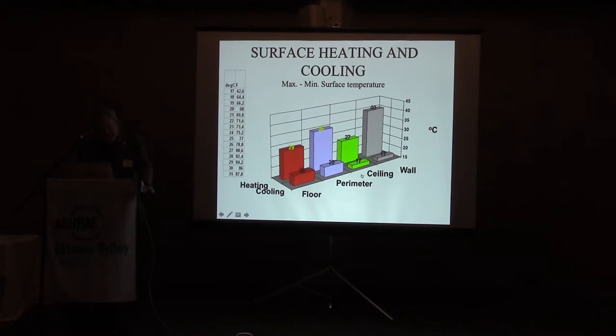Well, the ceiling, we don't have any parts of the body which are in contact with the ceiling. So here, the limitations for the heating part are the rate and the symmetry. People don't like to have a warm head and cold feet. The other way around, cold head and warm feet, is fine. So there are some limitations to how high a temperature they will accept from above. Normally the upper limit in a normal room is somewhere around 27, 30 degrees. But we have a method where you can calculate this asymmetry.